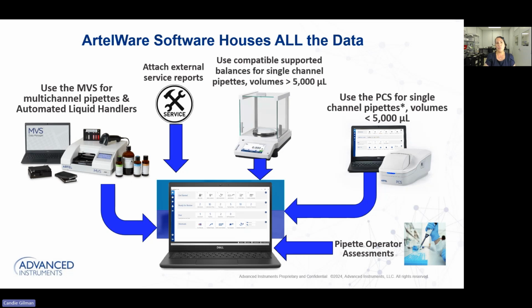But let's say you've got some larger volume pipettes in your laboratory, pipettes that are 10,000 microliters. How do you calibrate those? Our Artel software also has the ability to integrate supported balance models. So not just our MVS, not just our PCS, but also those supported balance models. And then also it has the ability to attach external records. So maybe you have to send a pipette out to a service because you've performed a calibration, you've changed the seal and O-ring on the pipette, and it still isn't passing. It needs a little bit of extra attention. You send it to a service center. The Artel application, that software, can house those external report attachments as well.